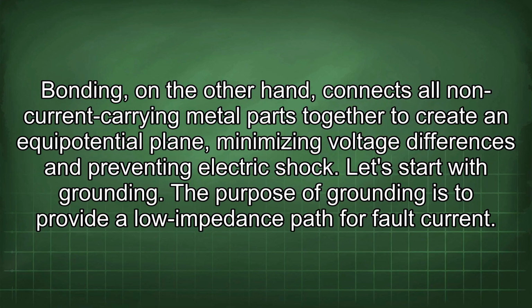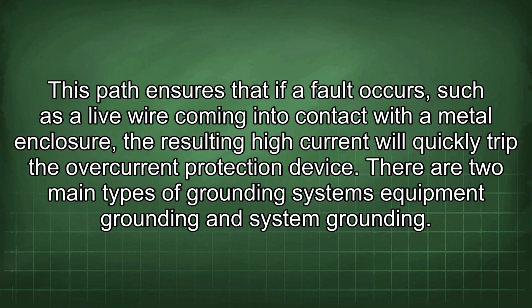The purpose of grounding is to provide a low impedance path for fault current. This path ensures that if a fault occurs, such as a live wire coming into contact with a metal enclosure, the resulting high current will quickly trip the overcurrent protection device. There are two main types of grounding systems: equipment grounding and system grounding.